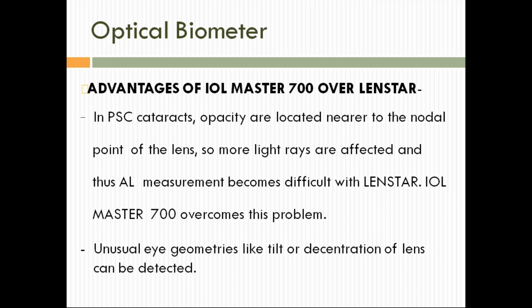And the next one is advantages of IOL Master 700 over LENSTAR. In PSC cataracts, opacities are located near the nodal point of the lens, so more light rays are affected, and thus AL measurement becomes difficult with LENSTAR. IOL Master 700 overcomes this problem. Unusual eye geometries like tilt or decentration of the lens can be detected.